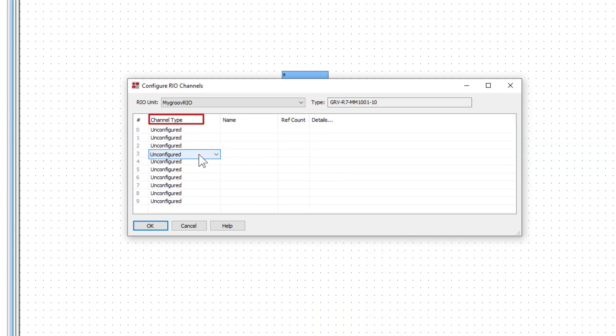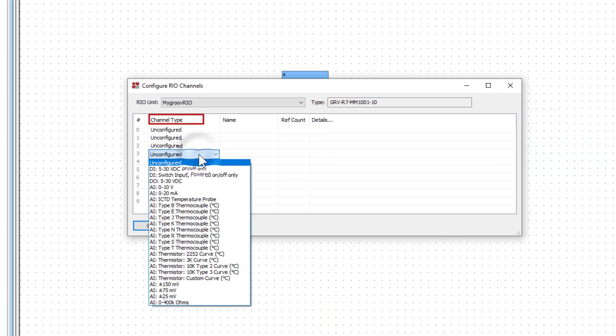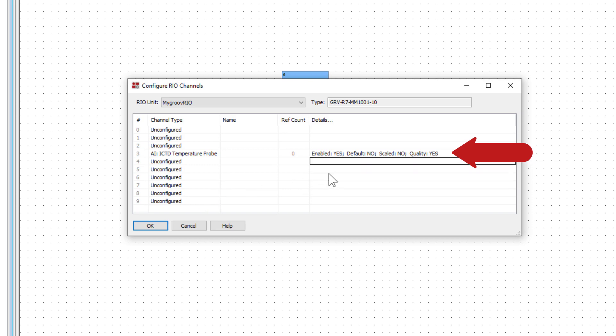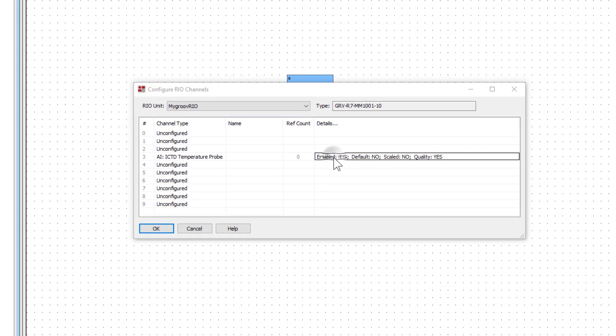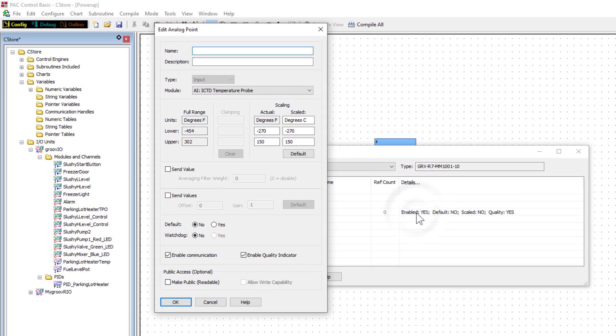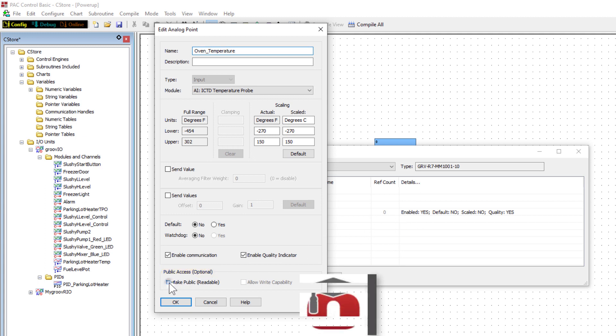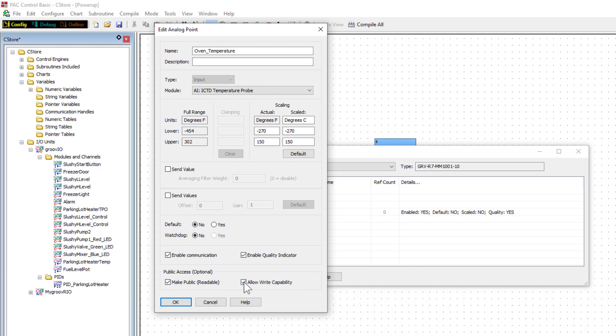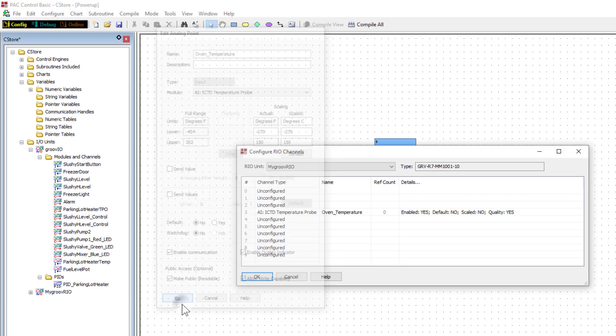Because of the way I have my two points wired to the field devices, I'm going to configure point 3 as the analog input and point 7 as the analog output. In the channel type column, click point 3 and select ICTD temperature probe. The default settings appear in the details column. Click the defaults in the details column to bring up the configuration window for the point. Name the point oven temperature. Let's give this point public access and make it readable and writable. By using the PAC control REST API, you can programmatically access the point with databases, Python, and many others.